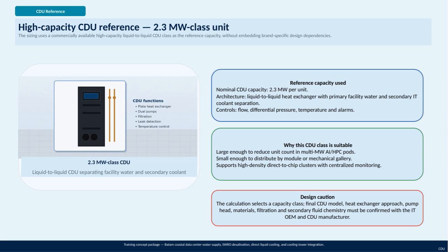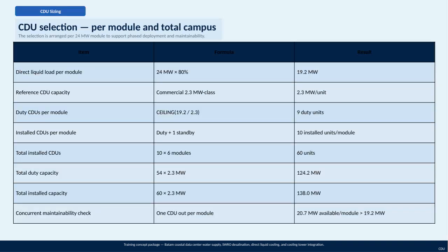compatibility and optimal performance. Here we're looking at the sizing and selection criteria for the cooling distribution units, or CDUs, which are critical for managing the thermal load at our Batam Coastal Data Center. The selection is organized for a 24 megawatt module, which allows us to deploy the infrastructure in phases and makes maintenance more manageable over time.